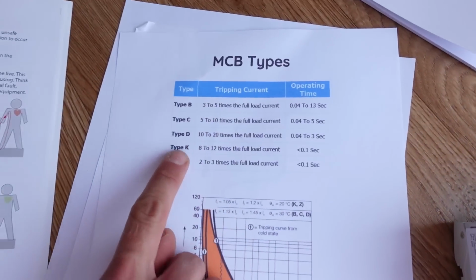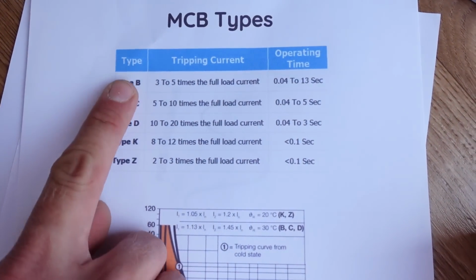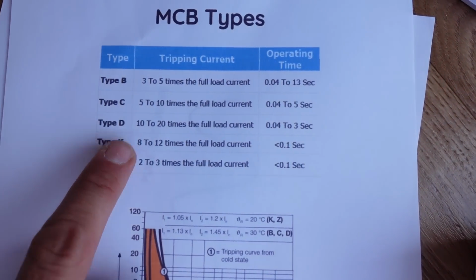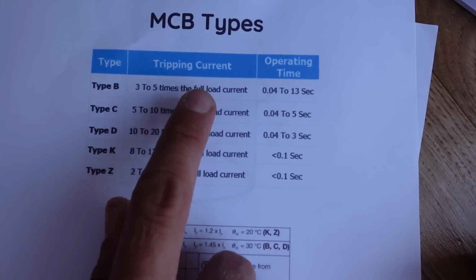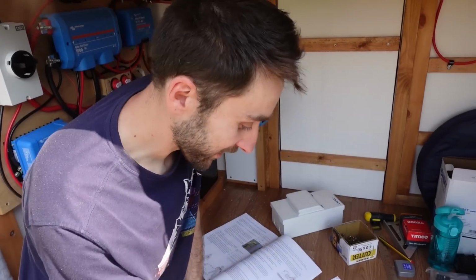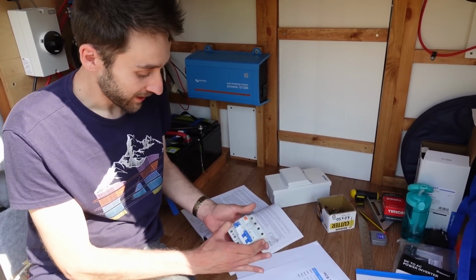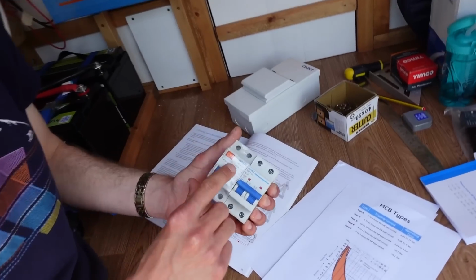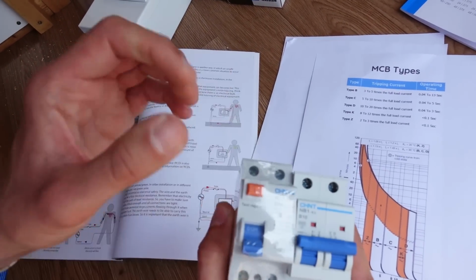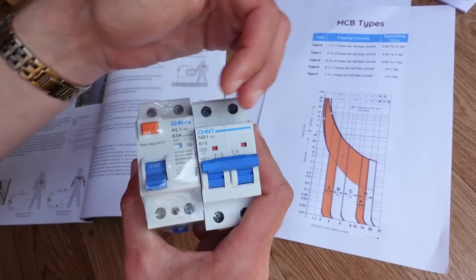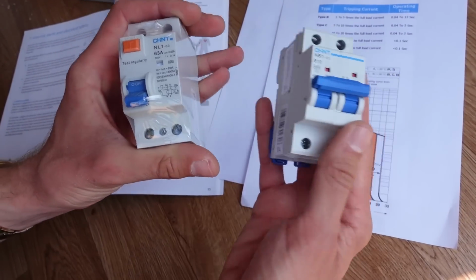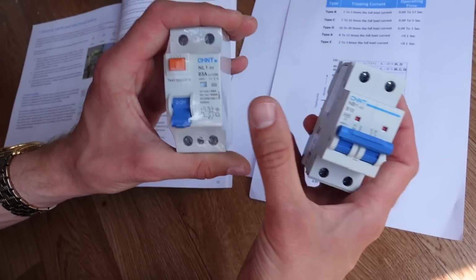So as you go up, if you've got something that needs a huge amount of surge power, then you might go up the MCB types. But for us and for most residential stuff, B is completely fine. And the last thing with it is the RCD also has an amp rating on it as well. And this one is 63 amps. And basically that just needs to be big enough to handle all of the expected load from the downstream MCBs. So this being 10 amps, the 63 amp is fine.